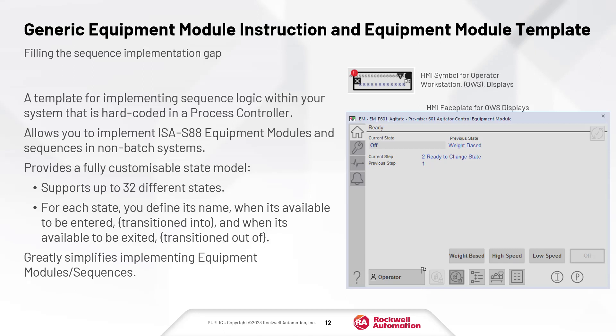The generic equipment module instruction and equipment module template is all about filling the sequence implementation gap. It is a template for implementing sequence logic within your system that is hard-coded in a process controller and is only available to use in our process controllers. It allows you to implement ISA S88 equipment modules and sequences in non-batch systems. It provides a fully customizable state model with up to 32 different states, each with their own name, configurable entry and exit conditions, and it greatly simplifies implementing your common modules and sequences.